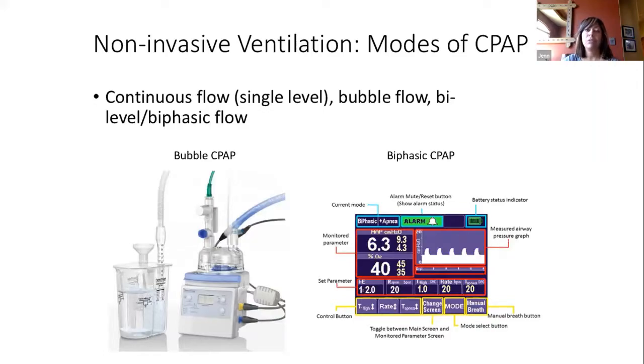This is a continuous flow, single level. You can do bubble flow or a bi-level biphasic flow. And here is an example of bubble CPAP. What is nice about bubble CPAP is it's a cheap alternative to a vent. So in resource limited areas, it's really nice. And then biphasic CPAP, so you can see that there's a rate, you have an I time, and you have different pressures that the ventilator is delivering.